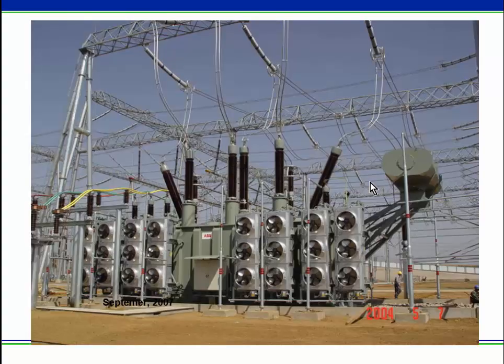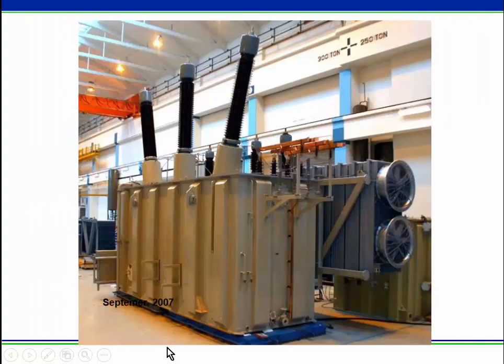So here's a picture of a massive power transformer. Cooling is a big part of making transformers work. Really, all electrical equipment is rated based on heat, right? If it gets too hot, insulation melts and you have a failure. So the trick to getting a lot of power through one of these is to try to keep it cool. At least that's one of the ways to do it.